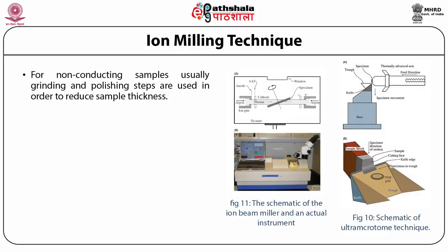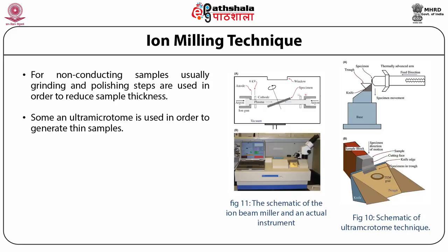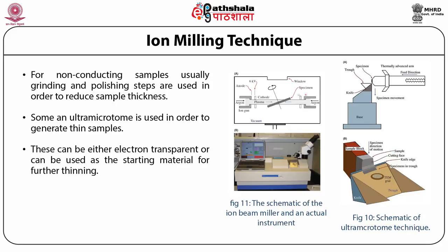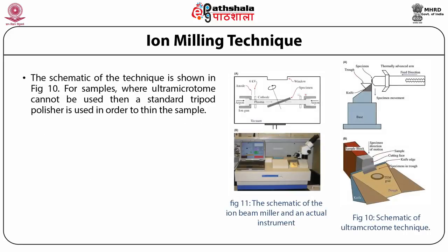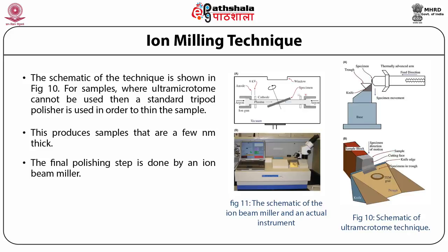The second technique is ion milling. For non-conducting samples, grinding and polishing steps are used to reduce sample thickness, and an ultramicrotome may be used to generate thin samples. These can be electron transparent or used as starting material for further thinning. For samples where an ultramicrotome cannot be used, a standard tripod polisher is used to thin the sample to a few nanometers thick, and the final polishing step is done by an ion beam miller.